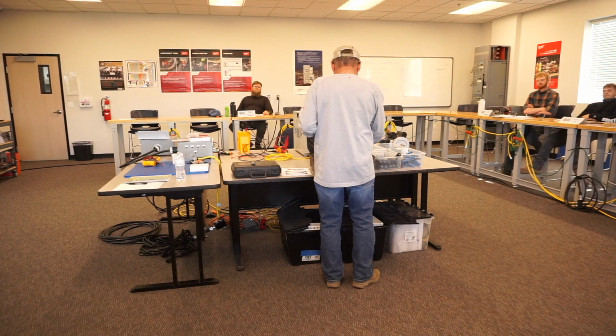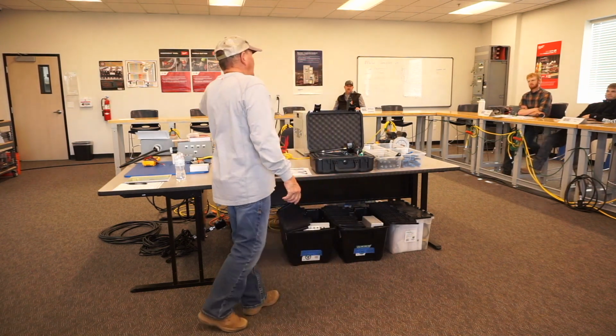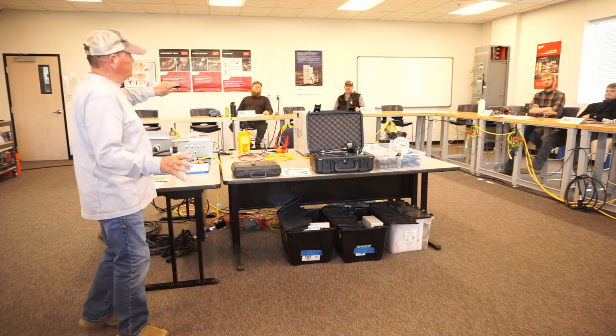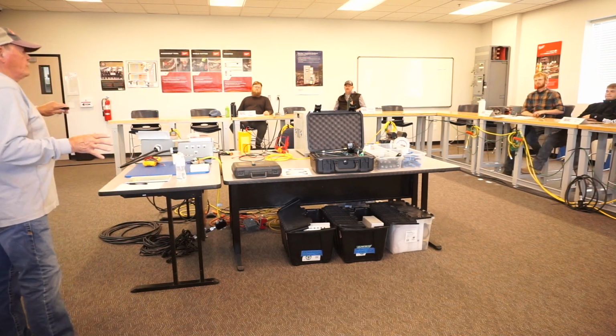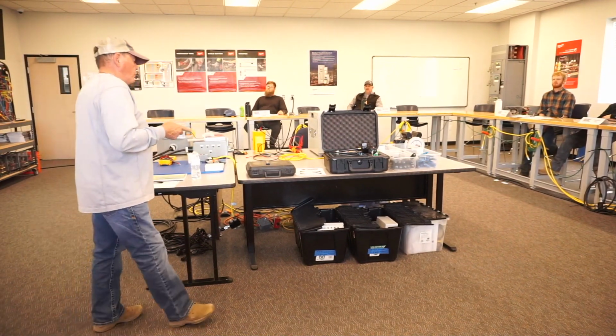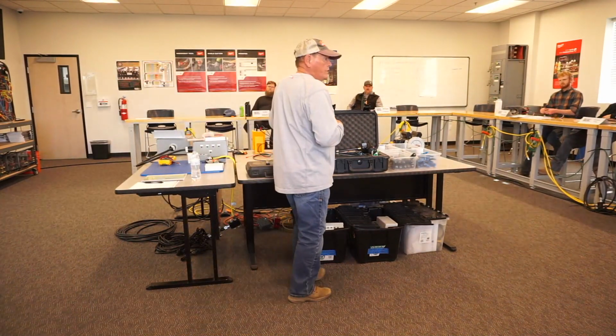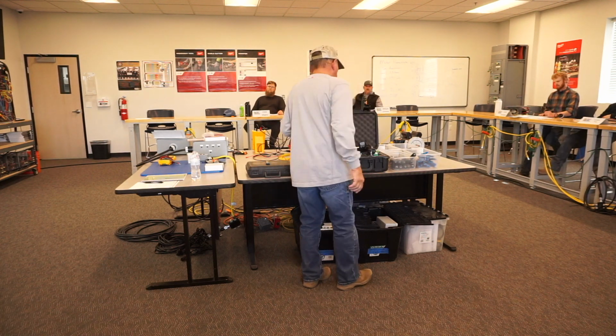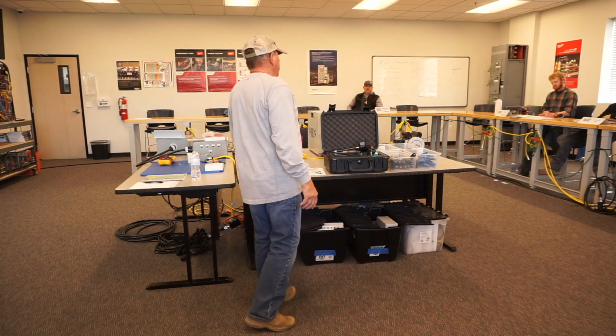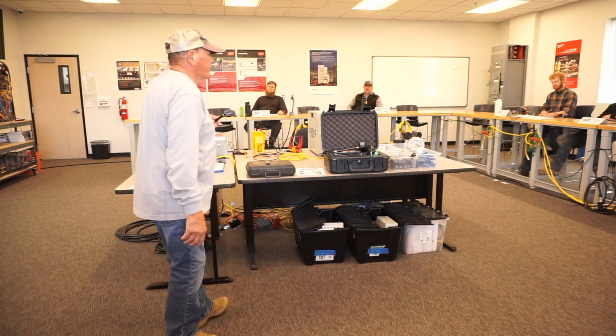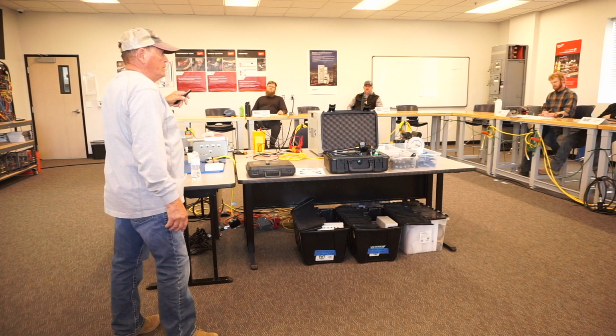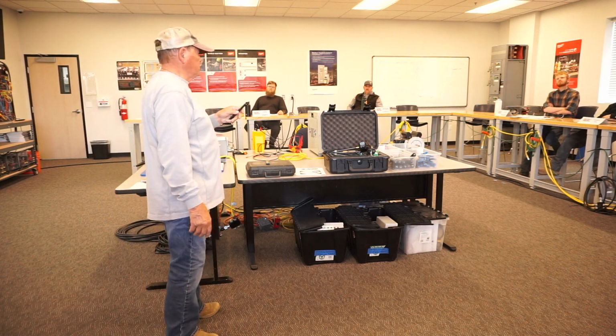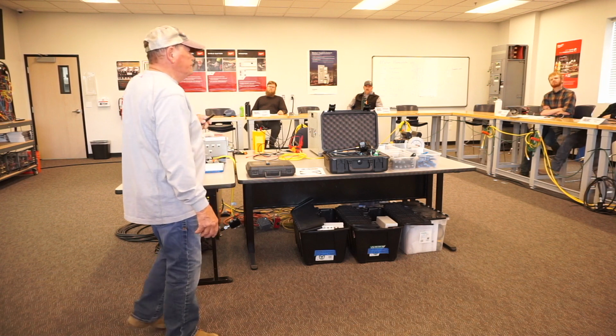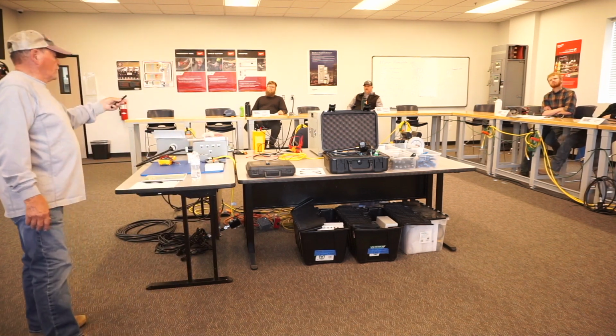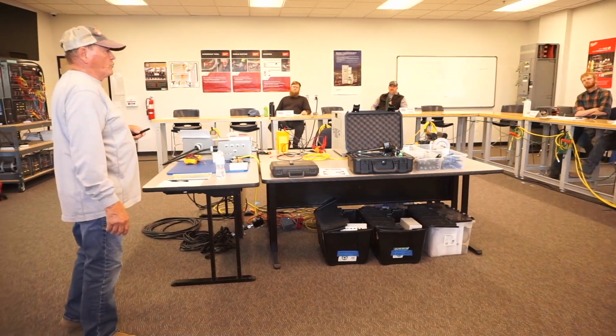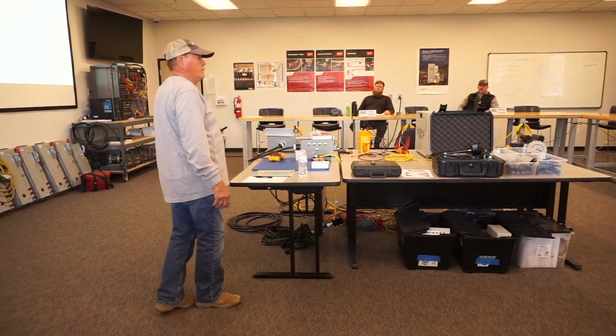Before they put those on, they hadn't bonded the motor. I said, you know, we've got to get these motors bonded. So let's test one. They had ABB drives. So I went out there and put the meter on one motor. We were getting about 3.5 volts discharging off the shaft of that motor. So they bonded the motor, and the voltage dropped to a little bit less than 2. I said, okay, let's put those guys on and see what happens. It dropped to less than 1. I said, oh, there must be something to it.